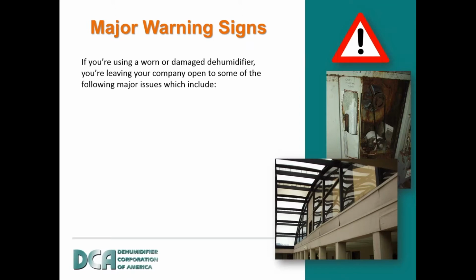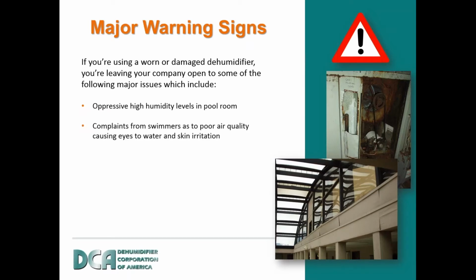Sometimes it's a little tricky to know whether the dehumidifier is actually operating correctly or not, only because if you're not familiar with what it sounds like when it's running, oftentimes the blower is always running, you're delivering air through the room, but the compressor is off. And when the compressor is off, of course, it's not doing any dehumidifying. So some of the early signs might be oppressive high humidity levels in the pool room, which is more than normal that you've experienced. And many times you're going to hear complaints from swimmers as to poor air quality, causing their eyes to water and skin irritation.